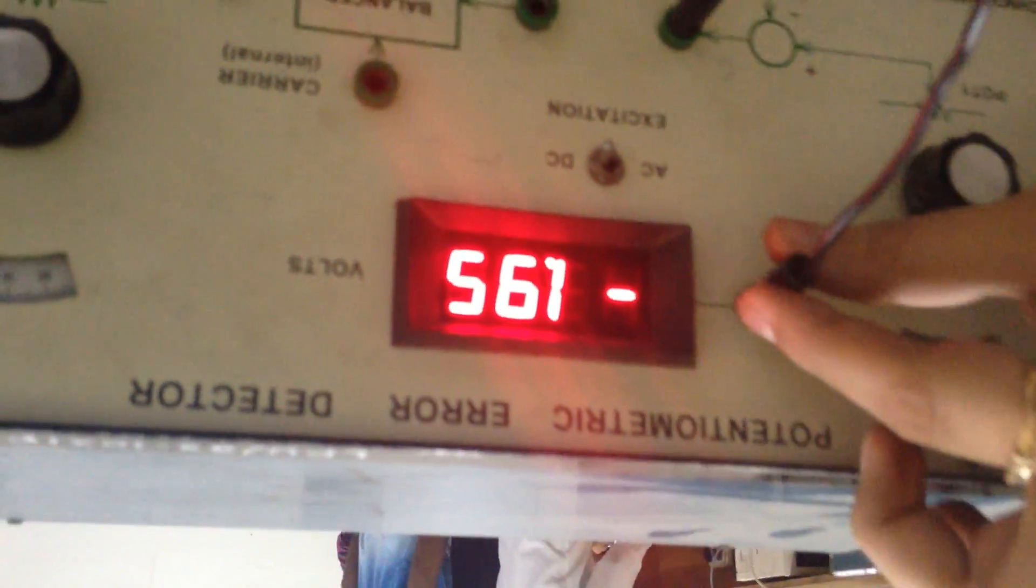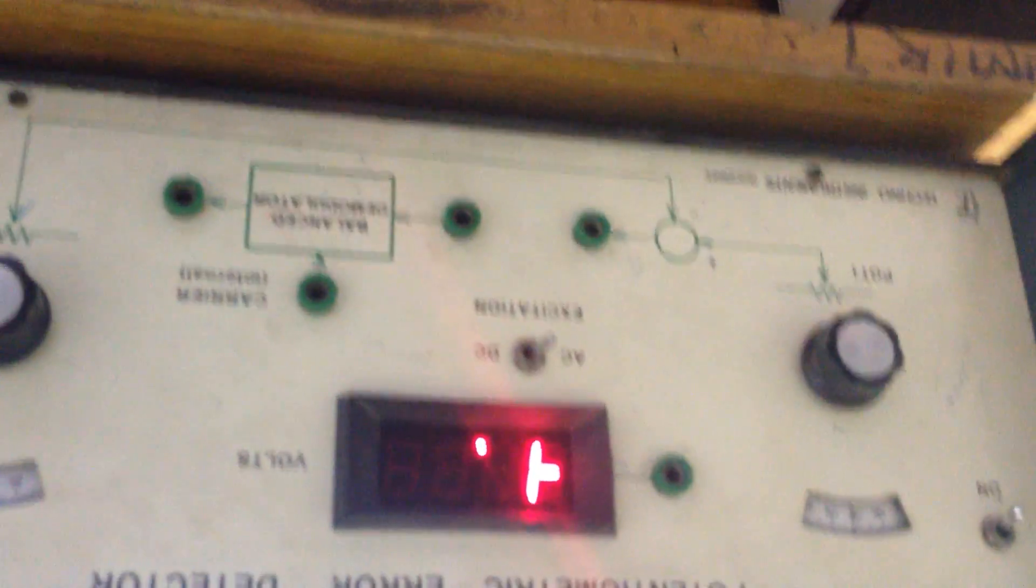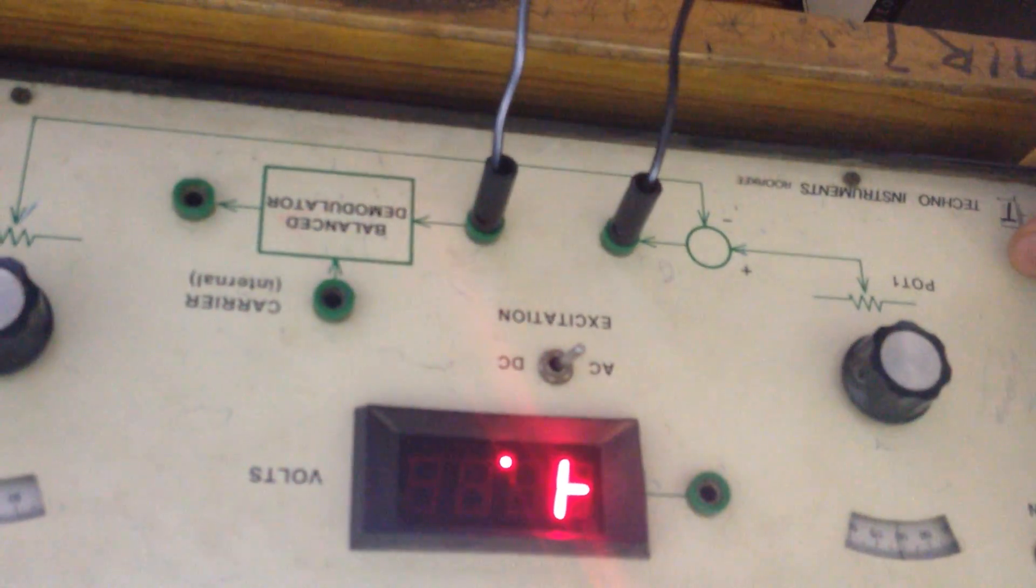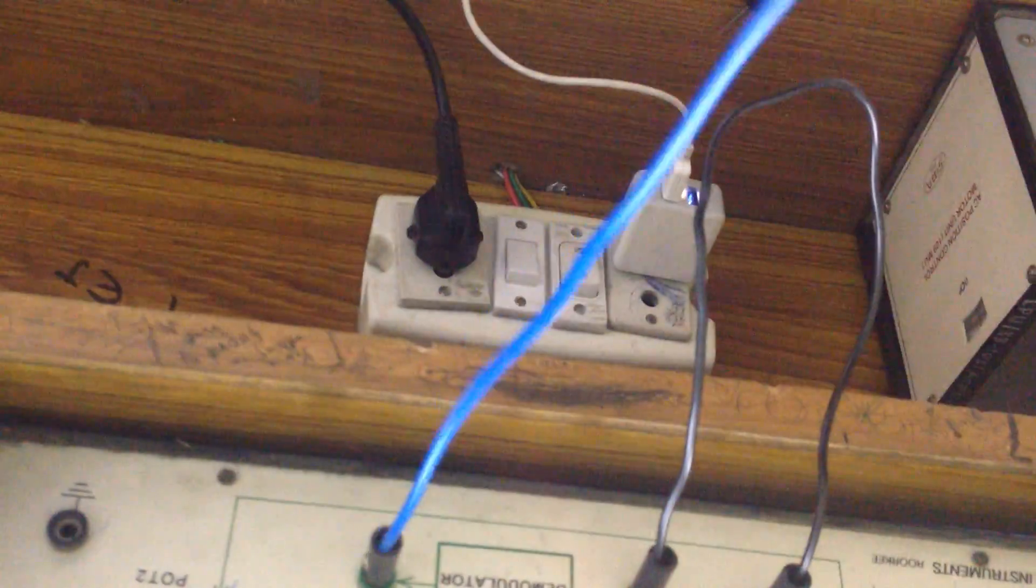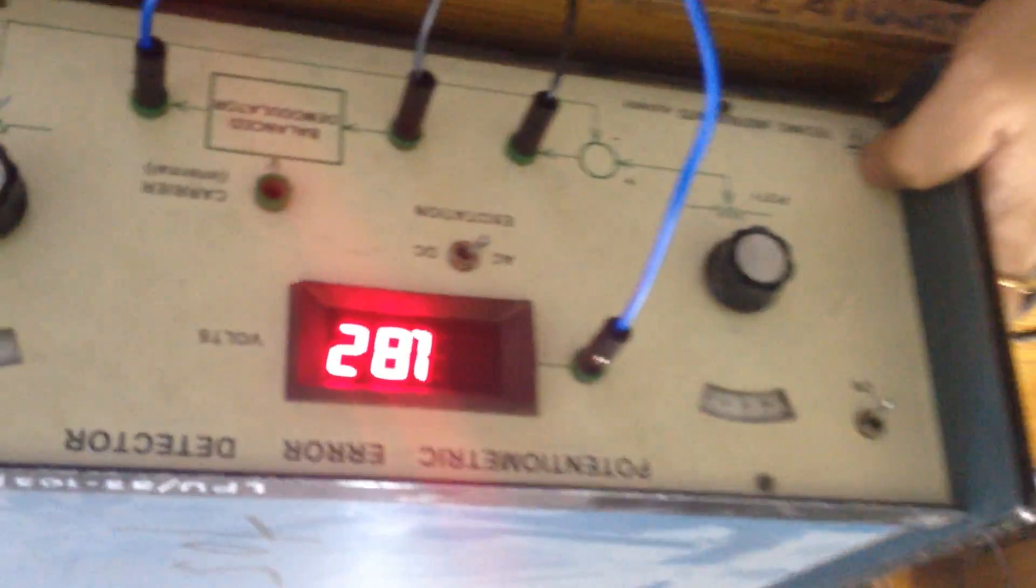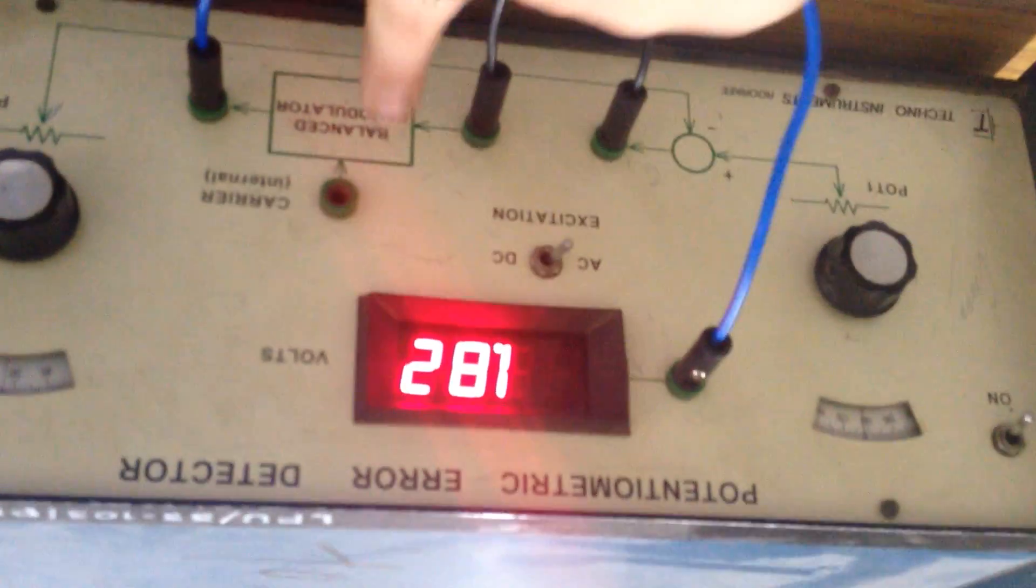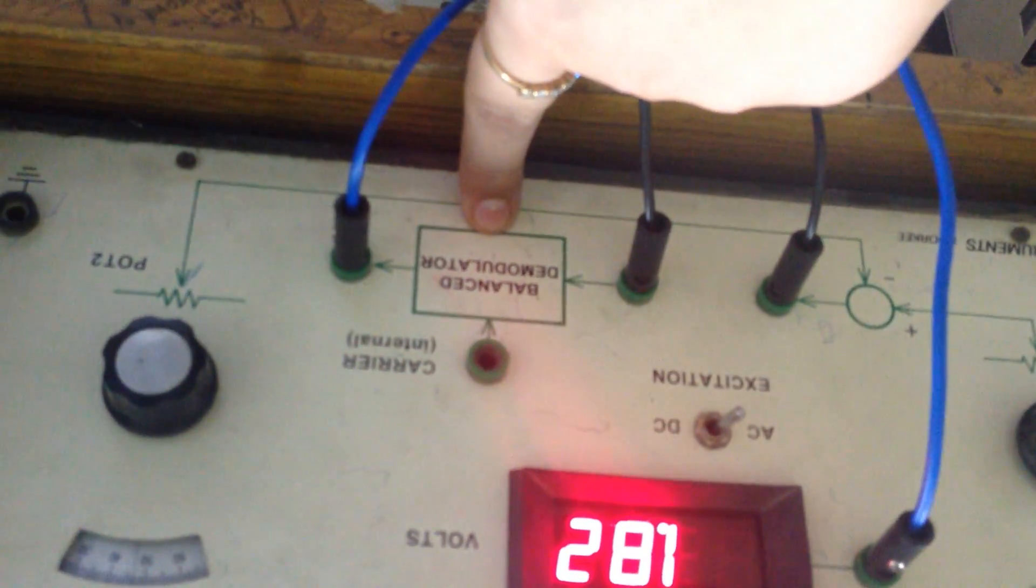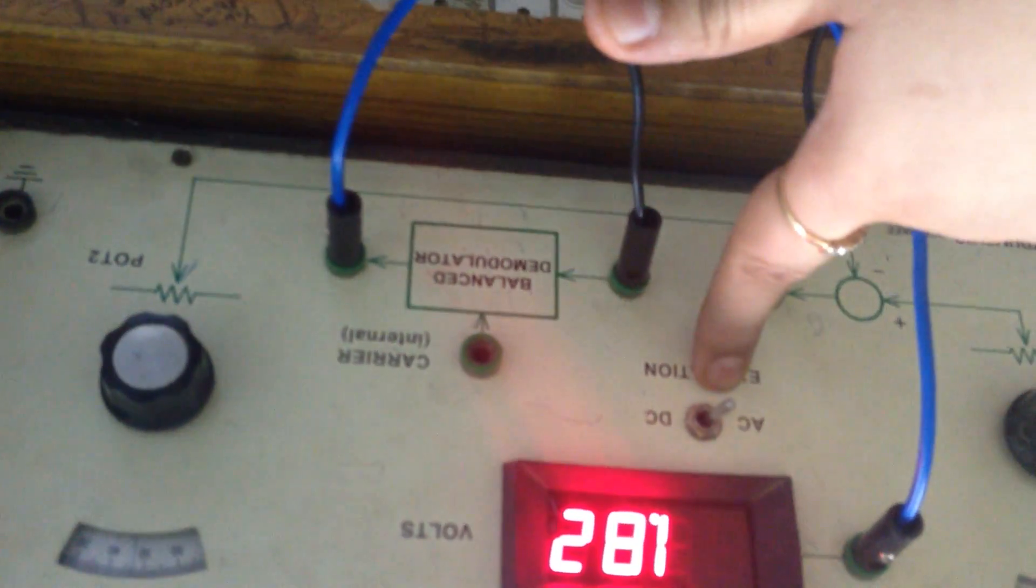Now when I give the AC excitation, I will have to connect a demodulator in between. This demodulator output is connected with the voltage display. This demodulator cancels the effect of the carrier wave because now we are using AC.